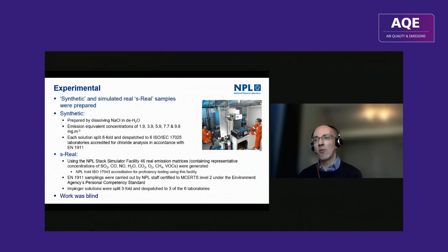There were a few matrices that were created going to higher concentrations and introducing some other interferences just to give some additional data. But for the most part, we simulated a waste incinerator type scenario. All the sampling of the stack simulator was carried out by staff qualified to level 2 under the MCERTS scheme.